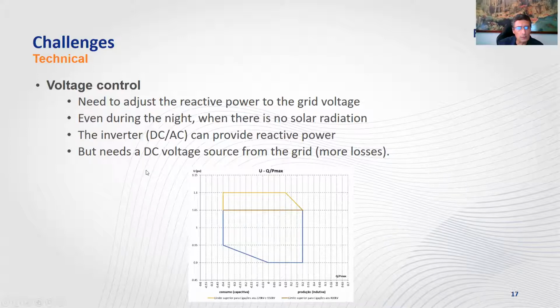Normally, on the distribution level and also the old power plants, they are controlled by tangent phi, so reactive power in proportion to active power. But for PV connected to the transmission grid, we already have plants providing voltage control, which means that if the voltage of the grid increases, they will absorb reactive power, and if the voltage decreases, they will inject it.